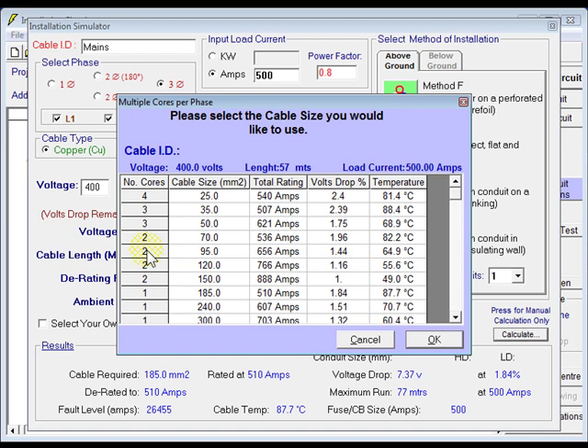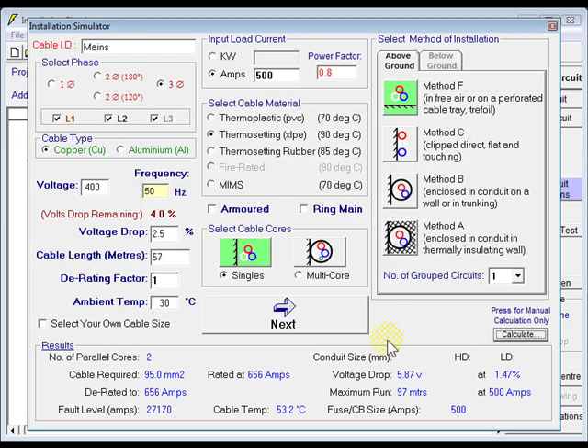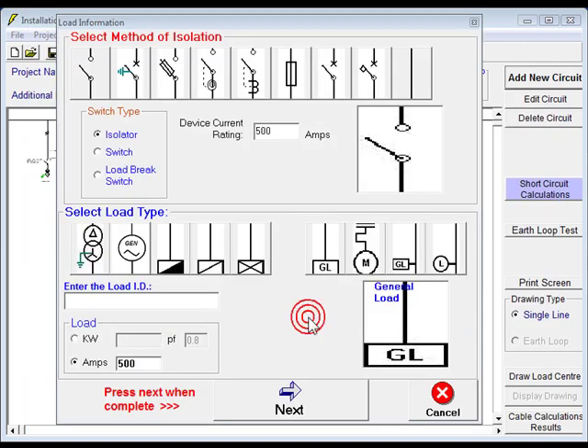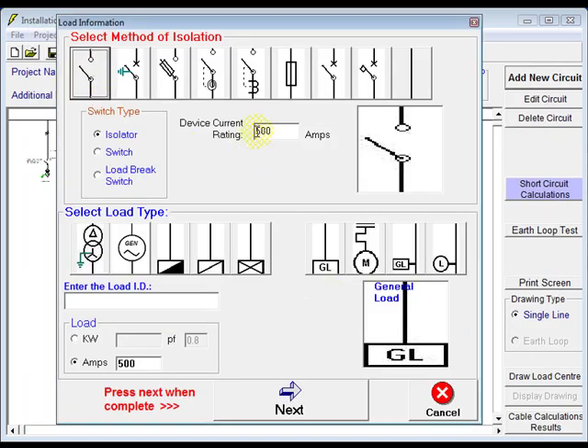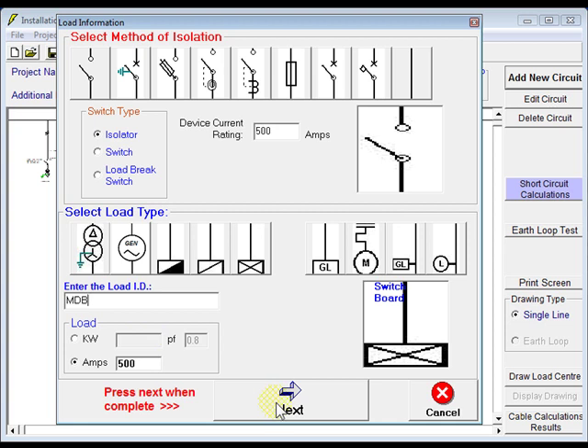We can have the 295s here, at 64.9 degrees, 1.44% voltage drop, which is probably going to be fine, so we'll use that one, and we click next. So we go to an isolator, 500 amps, goes to our main board. We'll just call it main distribution board, 500 amp load, click next.